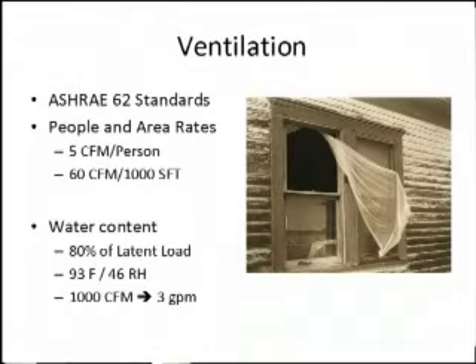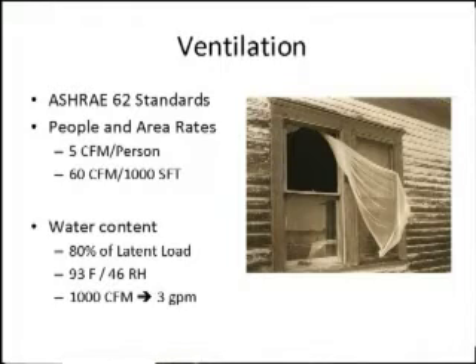And the standard has changed quite a bit over the years. When I first got in the industry, I think it was a flat 5 CFM per person for just everything, and then all of a sudden it jumped to 20 CFM per person. Everybody in energy freaked out and said, "You're going to end the world, ASHRAE." And so now the latest version is taking into account not only people but also space. They have an option where you can look at your square footage and they allow you to get back down to 5 CFM if you account for the space as well. So the current is 5 CFM per person and 60 CFM for every 1,000 square feet. So why do we want to ventilate for people?